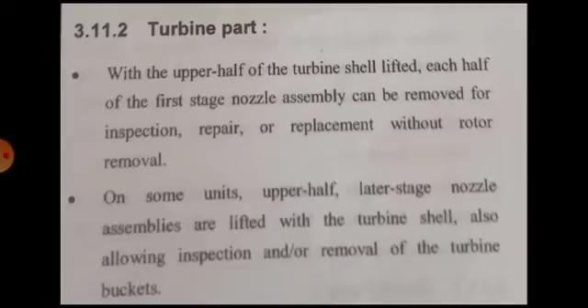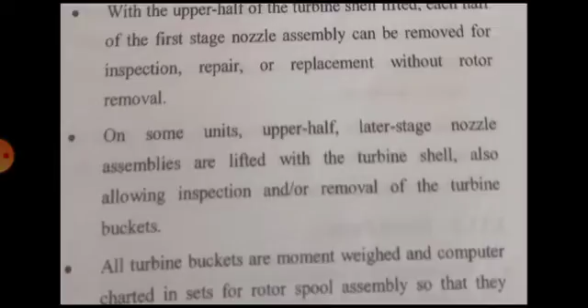Turbine parts, which are to be maintained with the upper half of the turbine shell lifted. Each half of the first stage nozzle assembly can be removed for inspection, repair, or replacement without rotor removal. On some units, upper half later-stage nozzle assemblies are lifted with the turbine shell, also allowing inspection and/or removal of the turbine buckets.